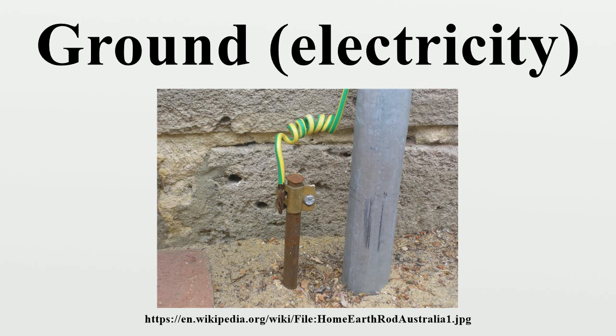A functional earth connection serves a purpose other than providing protection against electrical shock. In contrast to a protective earth connection, a functional earth connection may carry a current during the normal operation of a device. Functional earth connections may be required by devices such as surge suppression and electromagnetic compatibility filters, some types of antennas, and various measurement instruments. Generally, the protective earth is also used as a functional earth, though this requires care in some situations.